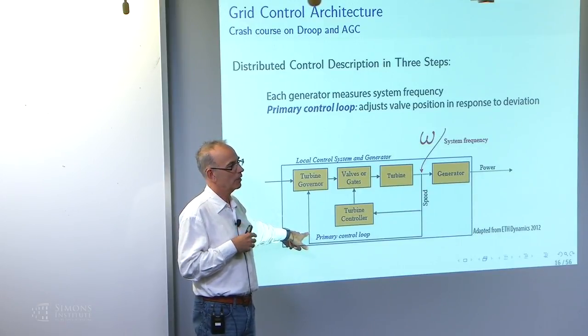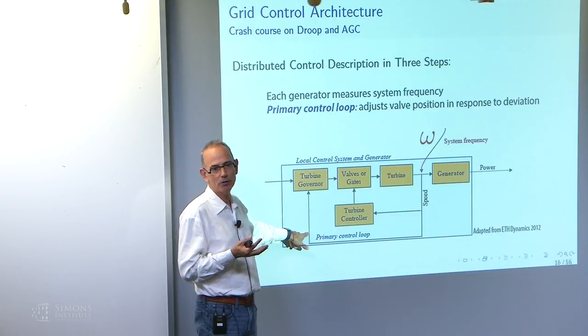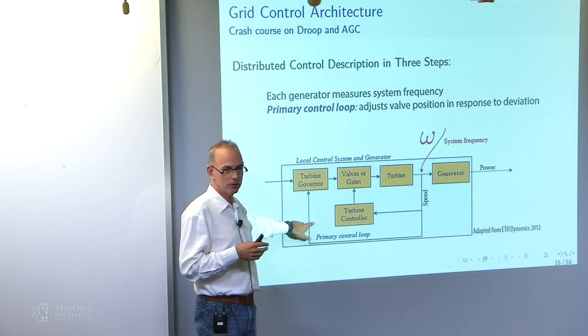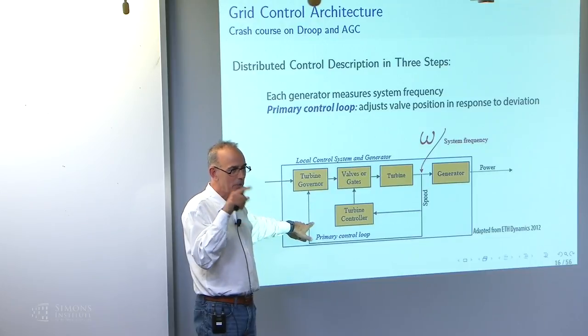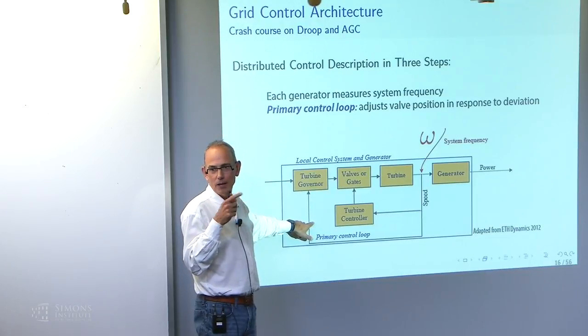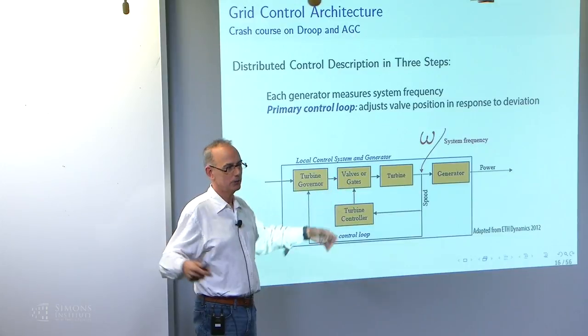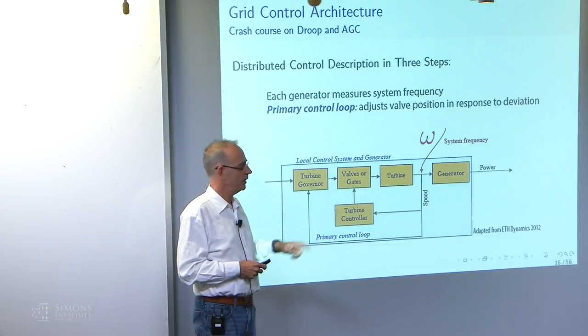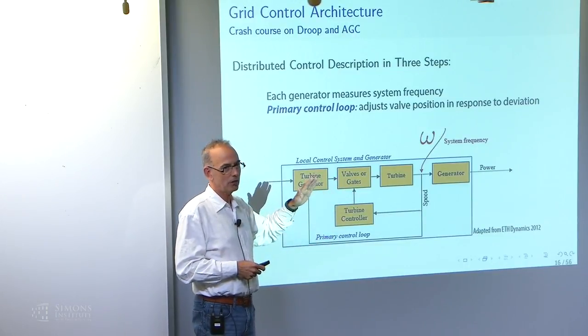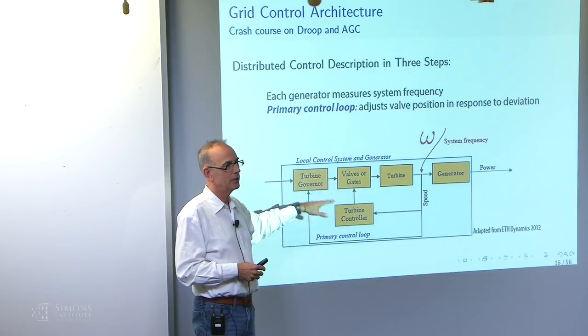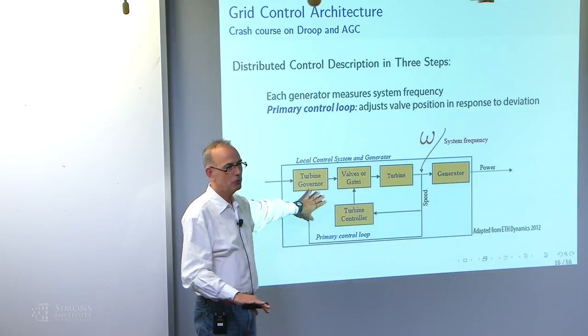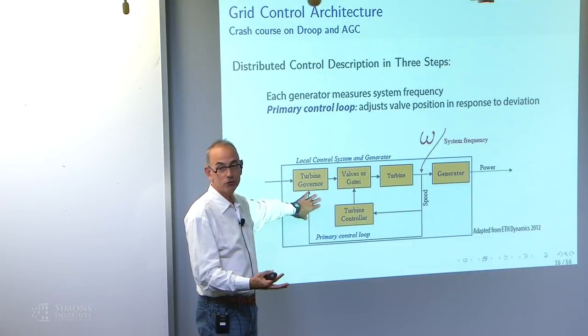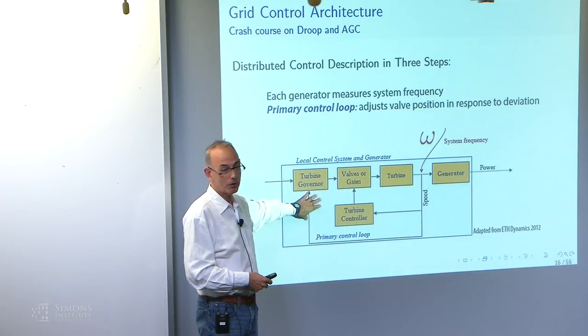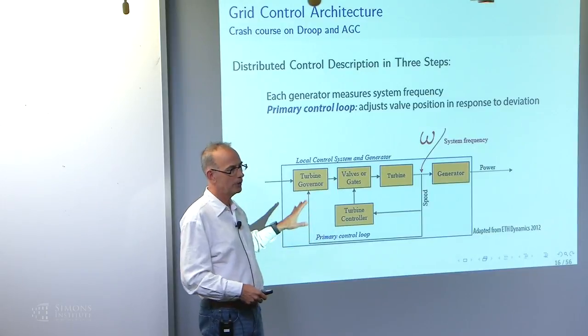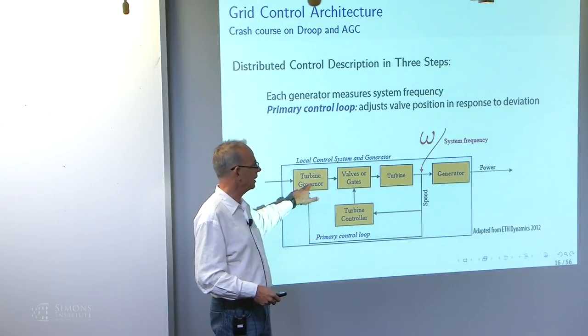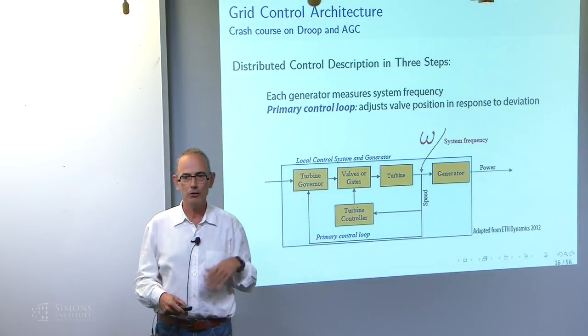There's a static analysis you'll mainly see in textbooks, but this is like the aileron trick - a little feedback loop at every generator to make the aggregate behavior nicer. Each one measures frequency and adjusts. So there's a static analysis that says this will help you not deviate too much in frequency, but the dynamics are being shaped as well by doing this. The details of this block diagram are important, just as important as measuring frequency and adjusting the amount of fuel going into the generator in response.